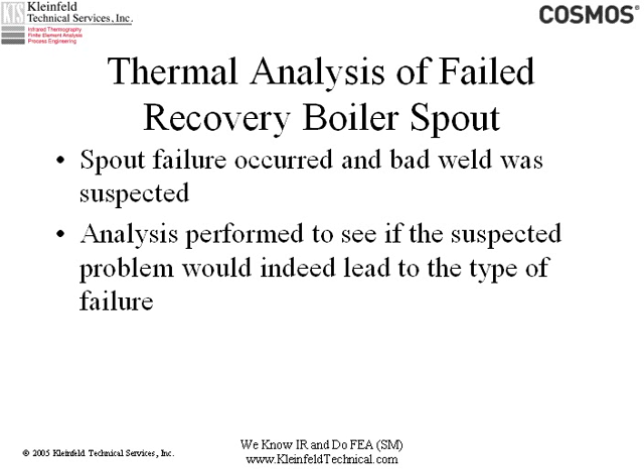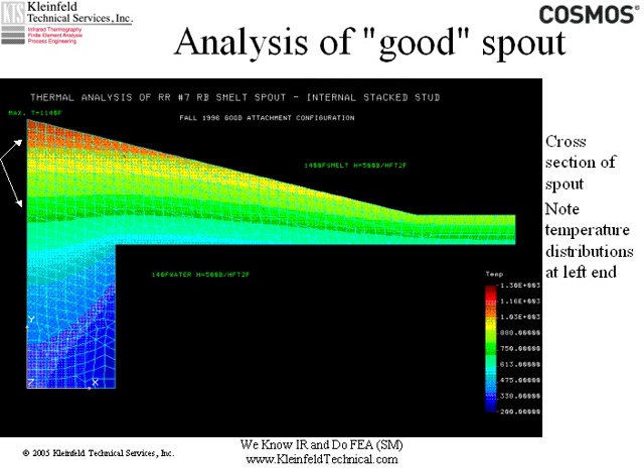We'll start off with the steady-state examples, and the first is a thermal analysis of a failed recovery boiler spout. Recovery boilers are used in the pulp and paper industry — they take molten salts out of the bottom of the recovery boiler, so these are very hot. They are water-cooled inside the spout, and the spout is an open spout where the smelt — the melted salt — runs. You don't want the water and the smelt to mix; it's a good way to blow up the boiler, and that happens with an unfortunate regularity. One of these spouts had failed and did cause a local explosion.